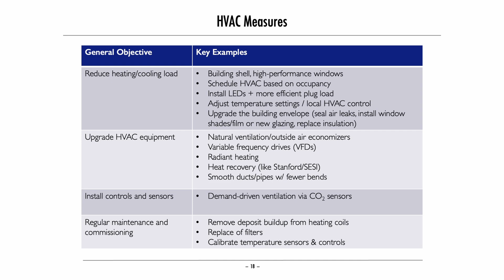We can also control it more precisely and make the job easier for our equipment—the heating and cooling equipment, air conditioners, heat pumps, and so forth. Those can also be made more efficient. They can be controlled in a way to do things like using outdoor air when it's cool enough to cool the building rather than refrigerating air. Pretty straightforward strategy, but engineers have to have a complicated name for it, so they call it an economizer. Not all buildings have been employing that, so it's a control upgrade when you do.